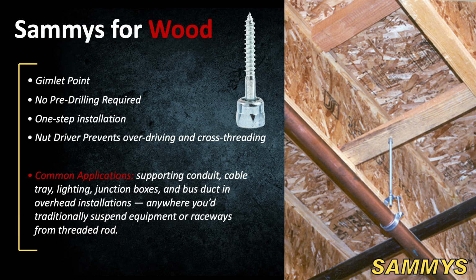Let's take a look specifically at Sammys for wood. These anchors feature a gimlet point and a design that doesn't require pre-drilling in many applications, which speeds things up. Installation is a simple 1-step process using the dedicated nut driver, which helps prevent overdriving and cross-threading. Common electrical applications include supporting conduit, cable tray, lighting, junction boxes, and bus duct from wood joists or beams. Basically, anywhere you would traditionally hang threaded rod from a wood structure.